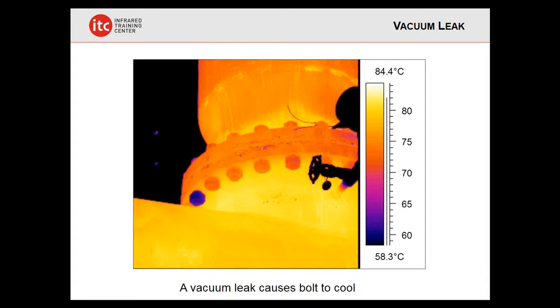And that pressure imbalance, as it was explained to me by Ron Lucier, could have had a pretty high price tag on it potentially, I think, because of what was happening. Yes, I don't recall exactly what the numbers were, but that bolt is cooled because of the adiabatic cooling of the pressure difference of the air there. It's a very dramatic thermal image. Again, this is something else that ultrasound can definitely locate and identify.